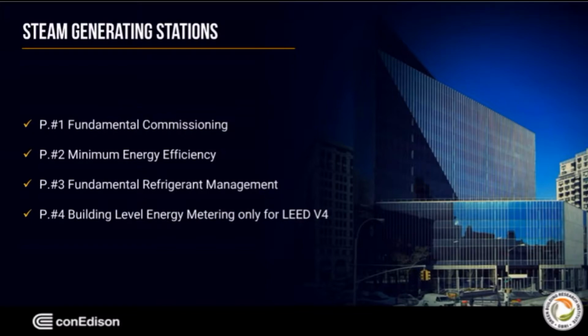First, let's go briefly over the prerequisites. For Prerequisite 1, a commissioning agent must be hired to commission the facility and show that it operates as intended. Only downstream equipment needs to be commissioned, which is all heating and cooling systems, any equipment associated with transporting the thermal energy from the DES into the building.